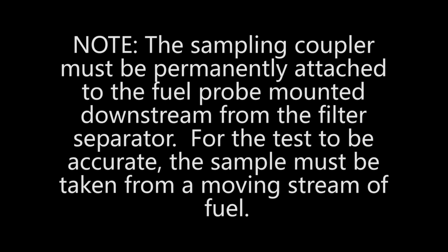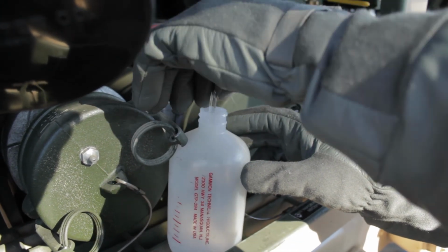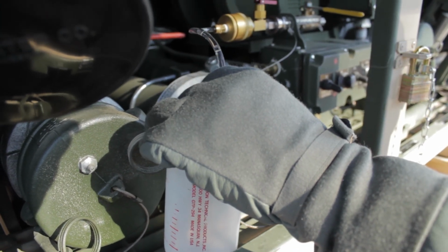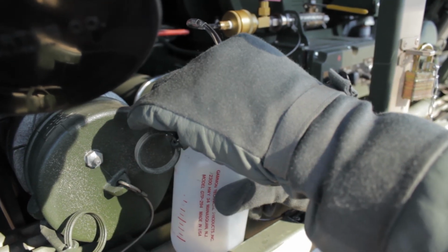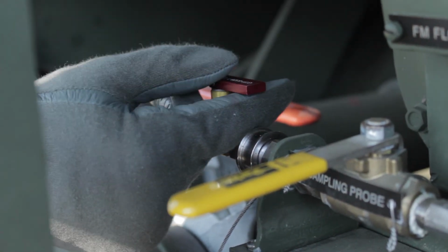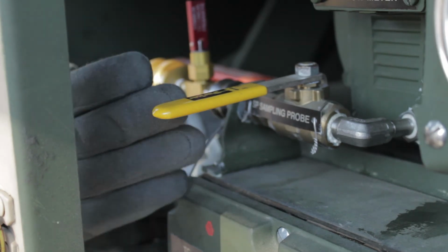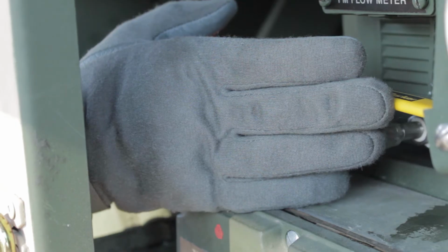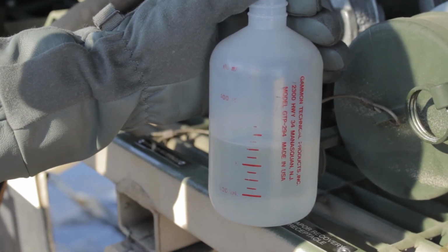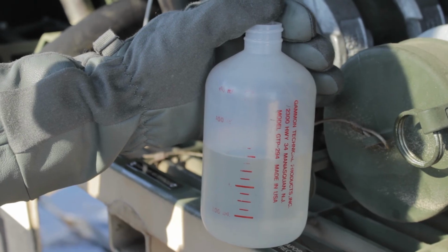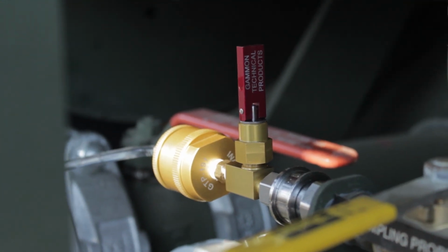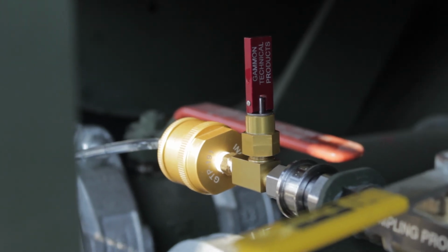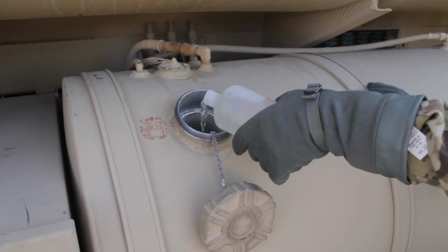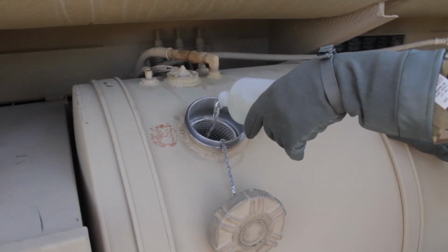For the Aqua Glo test to be accurate, the sample must be taken from a moving stream of fuel. Ensure that the plastic discharge tube of the fuel sampling test adapter is put into a plastic container. Move the toggle valve on the sample test probe to the open position and connector to the open position, parallel to the line. Flush 1 liter, 1,000 milliliters, of fuel through the sampling test probe into the plastic container. Move the toggle valve on the sample test probe to the closed position and the connector to the closed position, perpendicular to the line. Empty the plastic container into the equipment fuel tank or a waste container.